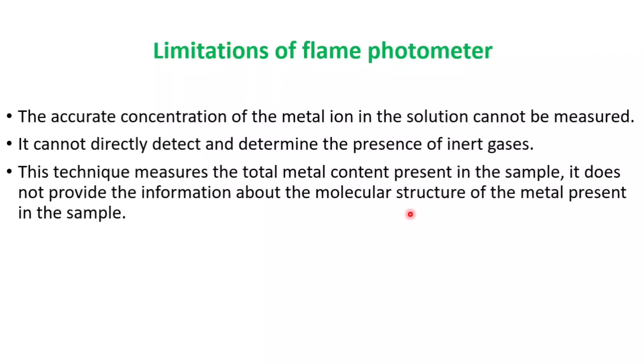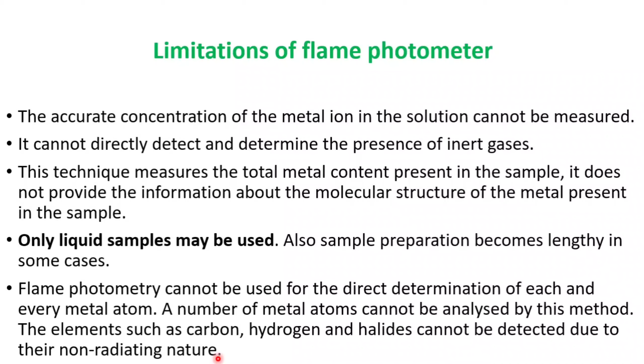Only liquid samples may be used in flame photometer. Also, sample preparation becomes lengthy in some cases. Flame photometry cannot be used for direct determination of each and every metal atom. A number of metal atoms cannot be analyzed by this method. The elements such as carbon, hydrogen, and halides cannot be detected due to their non-radiating nature. It's about limitation of flame photometer.